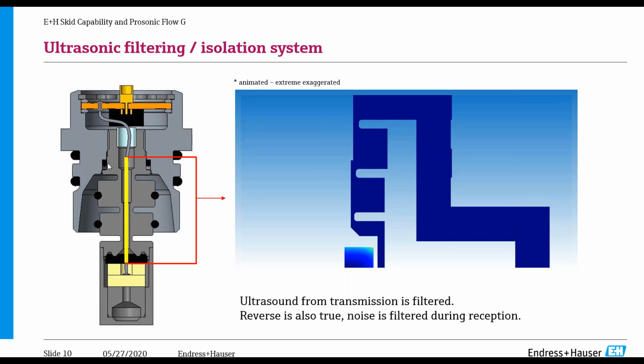So here what we've done, again, piezos are here. We're going to see this popping up in the animation in a second. And we have these masses that filter out the ultrasonic signal. So we start vibrating, and these mass blocks actually start to dampen out the ultrasonic signal, stopping that from traveling outward and creating noise within the system. And what happens also, we see here the piezos are vibrating, but if we're getting ultrasonic noise from other things like valves, those type of things, these mass block filters actually work in the opposite direction also to protect our piezos so that they're only receiving the true flow signal values.